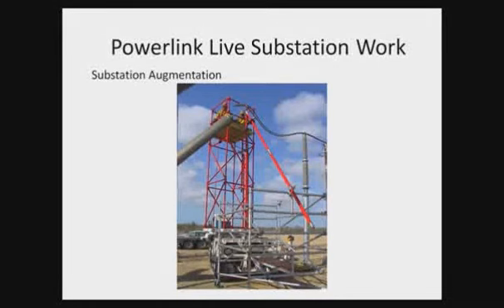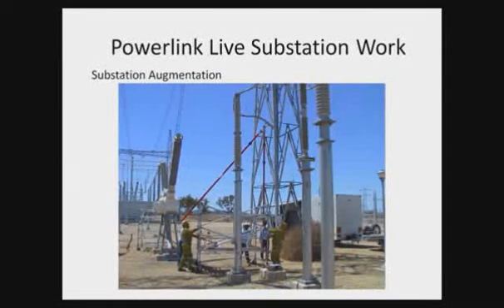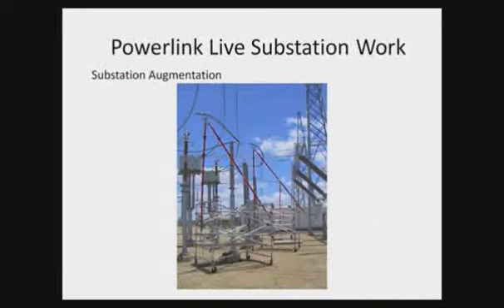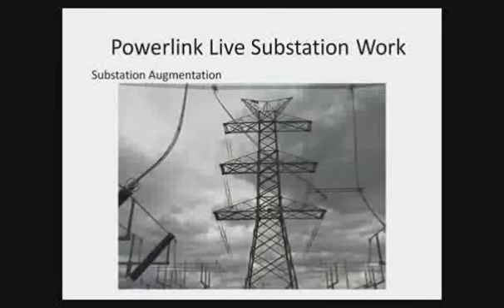And disconnecting circuit breakers, this particular type of circuit breaker, a PAS unit that we have at Powerlink. So again, you can see the conductors are maintained by those hot sticks that are mounted on the scaffolding and moved out of the way so that we can change over that circuit breaker that has an issue. There you go, there's all three phases held back out of the way. And if you actually look closely at those three phases, go through those line traps and straight up and out on the feeder. So that's keeping that feeder in service, fed from the other side basically.